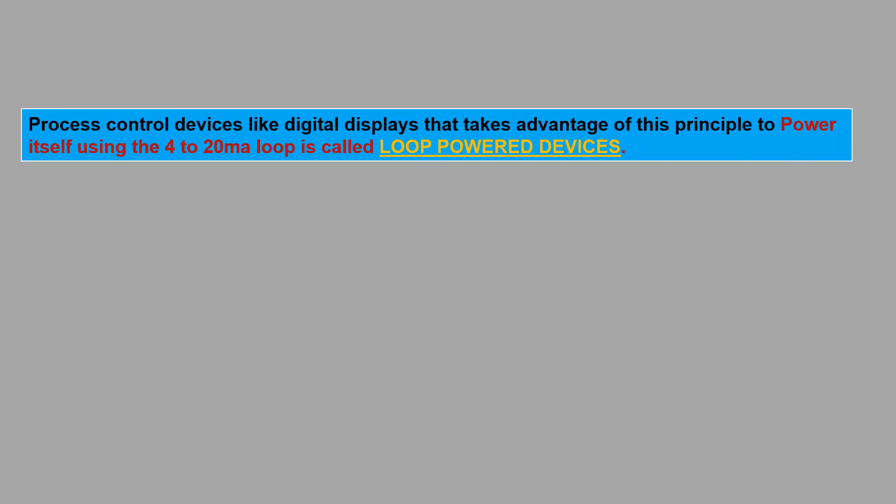Process control devices such as digital displays that take advantage of this principle to power itself using the 4 to 20 mA loop is called loop-powered device.